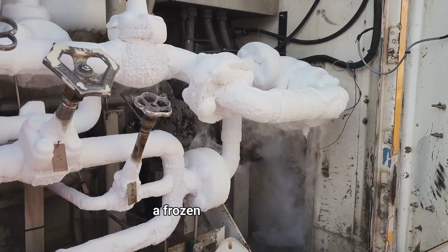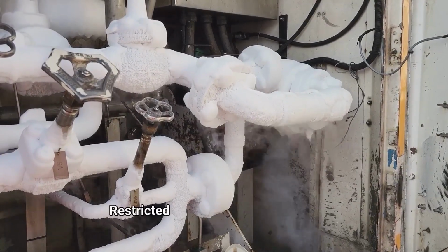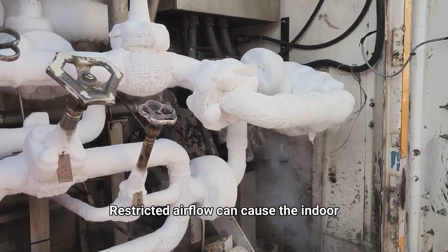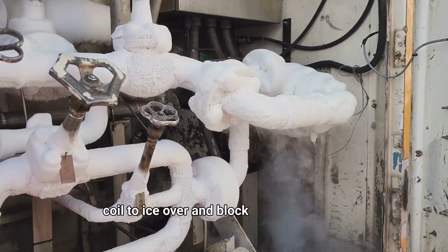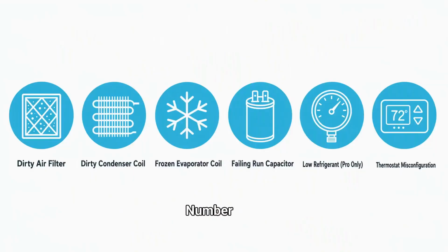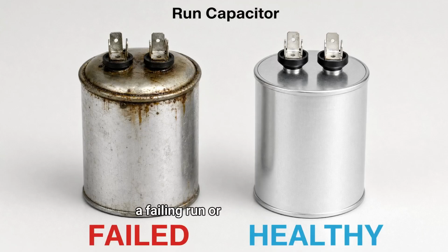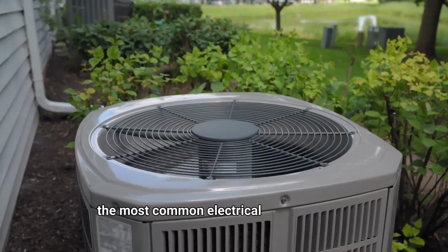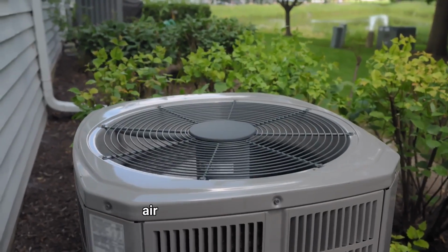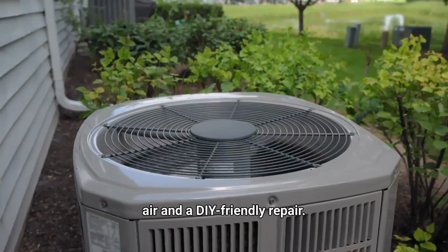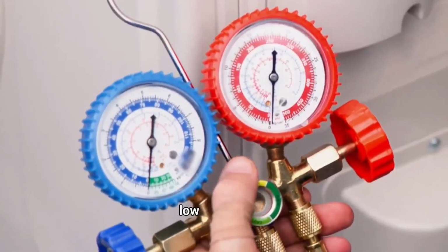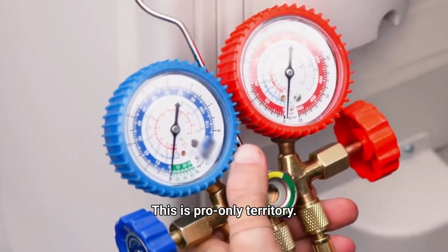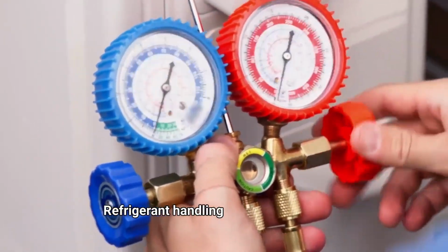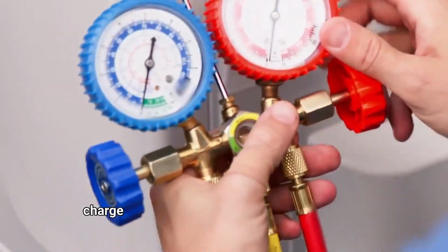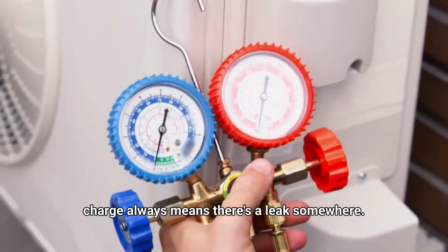Number 3, a frozen evaporator coil. Restricted airflow can cause the indoor coil to ice over and block cooling entirely. Number 4, a failing run or start capacitor. This is our main focus today, the most common electrical cause of warm air and a DIY friendly repair. Number 5, low refrigerant. This is pro-only territory. Refrigerant handling is regulated and low charge always means there's a leak somewhere.